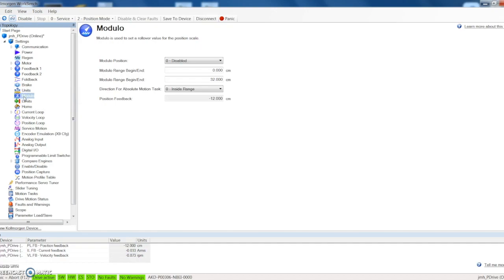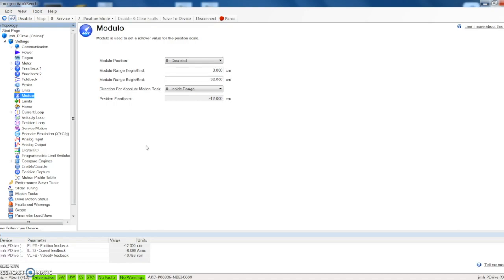Modulo is a pretty cool feature. If you were running a servo motor in one direction only, so you were doing a rotary index table and it's always going to index in the same direction, it's never going to reverse directions, that means that the encoder pulse count is always going to be going in the positive direction. It's never going to be able to go in the negative direction and count down. So what will happen is that you will eventually use all of your encoder pulse counts and it will reset itself to zero once you surpass that limit. That's not so good when you're trying to hold tight position. You could throw yourself off. Well, modulo lets you do is go in there and reset that value back to zero whenever you want to call it. So that's a really nice feature.